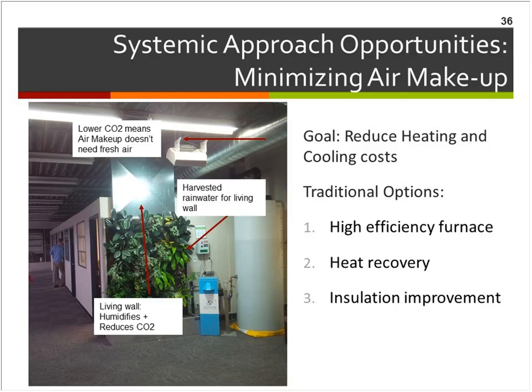Fresh air is often needed in a building because of CO2 from people breathing. The living wall reduced the amount of CO2 in the air, so there's no need to bring in fresh air. That reduces the natural gas and electricity needed. The living wall requires water, so we tapped into one of the rain leader downspouts running through the office and collected rainwater to service it.